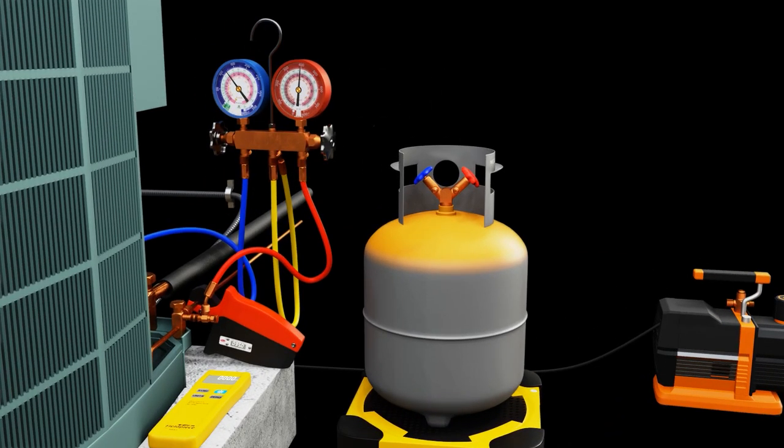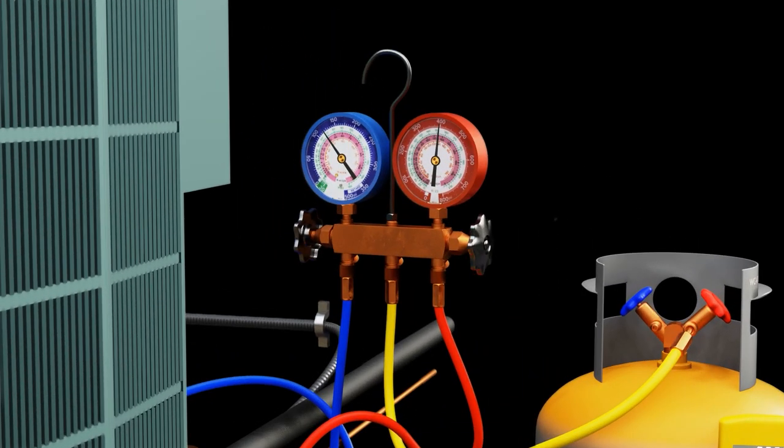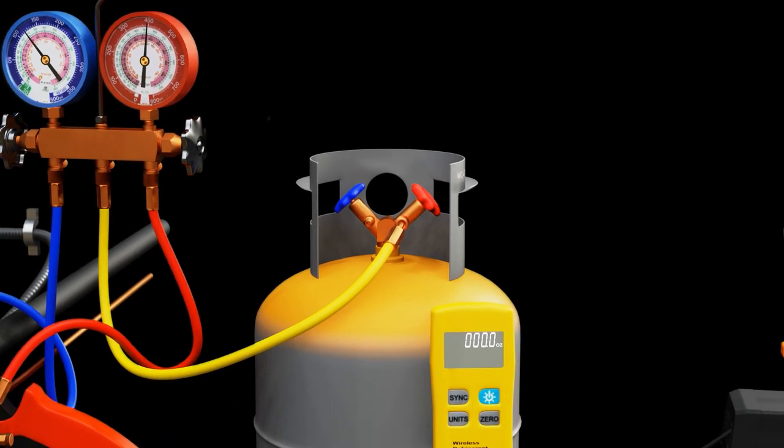We put the tank on the scale. And now we zero out the scale. You can see I'm connecting my center hose to the liquid gauge, I'm opening the valve. And then I'm going to purge a little bit of refrigerant before I open the tank. You could also do it in an opposite direction. We want to make sure that we get the air out of the hose.